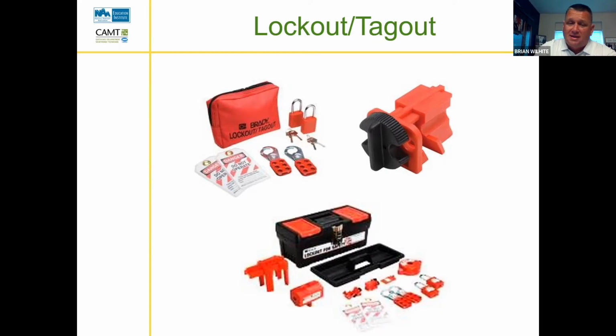If you are the one that is locking it out and tagging out, you're the only one that should have a key to that lock. And so nobody else has the opportunity to do that. Now, lockout tagout we use here in electricity, but we can use it for any kind of power source. And when we get into plumbing and other things, lockout tagout could be a water shutoff, a spring, thermal, whatever, pressure, electrical. We can lock out all those things. So don't be fooled that it's just an electrical thing. It's an every power source kind of thing that can cause harm to our bodies or to our property.